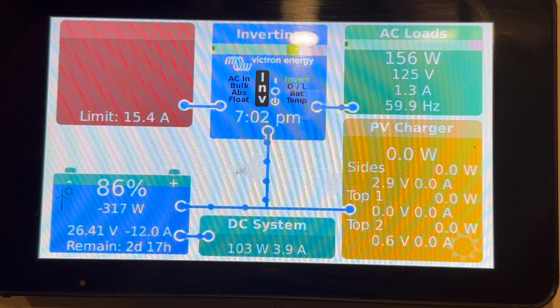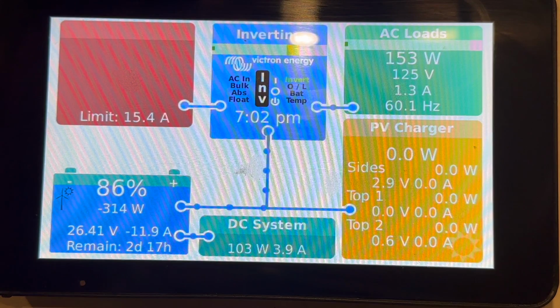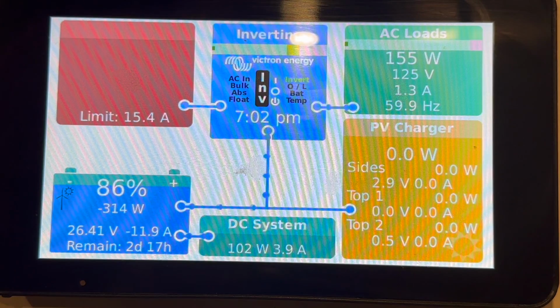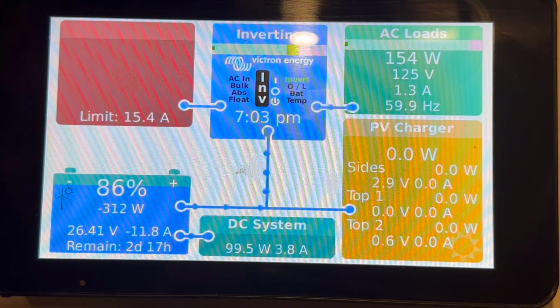The classic symptom is the voltage slowly climbing near 14 volts. I've seen this as early as 13.8 on a 12 volt system, and then it will instantly go to the absorption voltage, which is typically about 14.6. And if you're looking here, this is a 24 volt system, so we're at 26 volts right now. When you see that voltage go to 14.6, that means there's no more charge going into the batteries because the BMS has cut off charging.